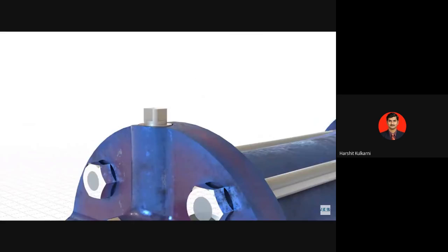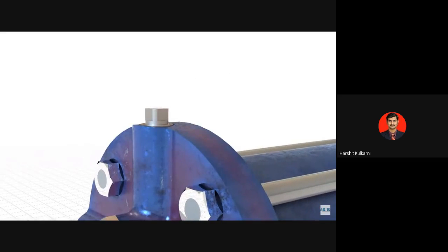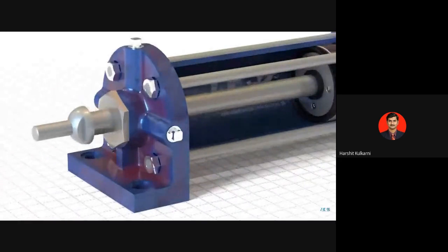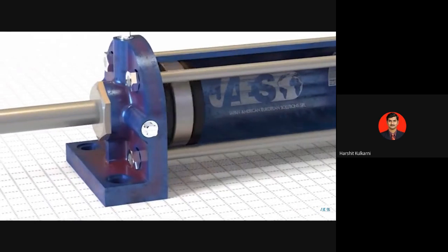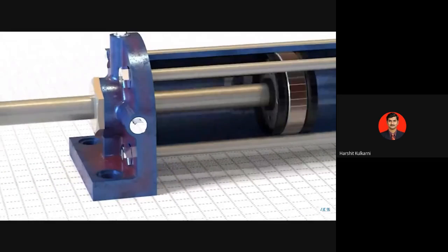A double-acting pneumatic actuator or cylinder has two holes which allow pressure to be applied for movement of the piston in the opposite direction than the one created by the first outlet. Generally, the larger the cylinder hole, the greater the output in terms of strength.